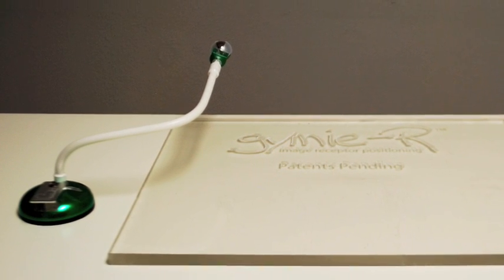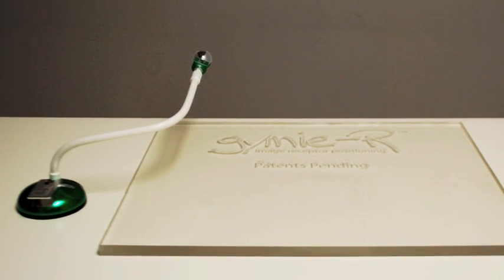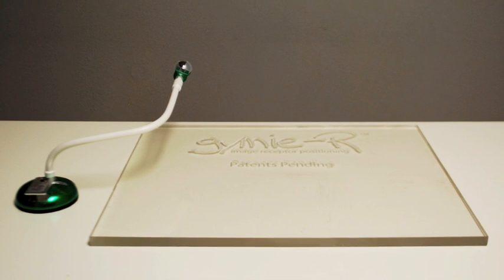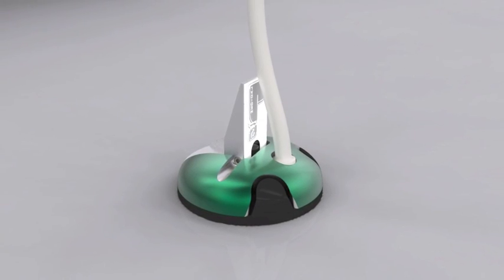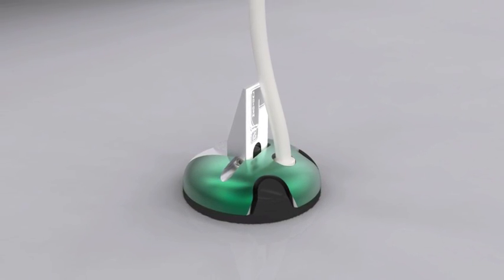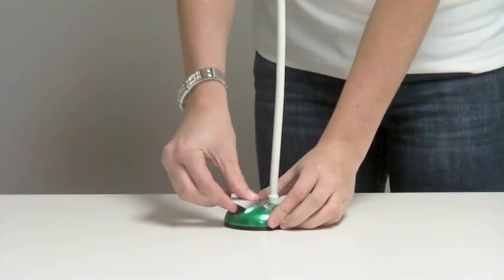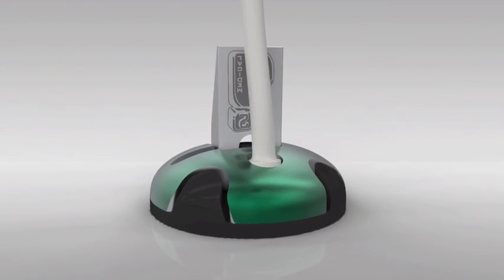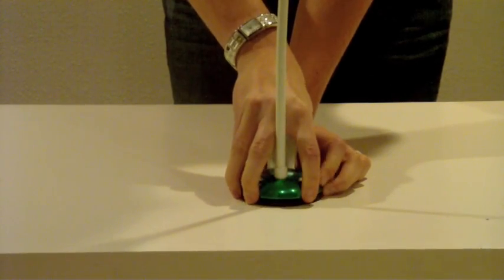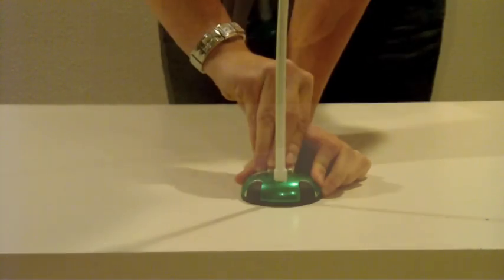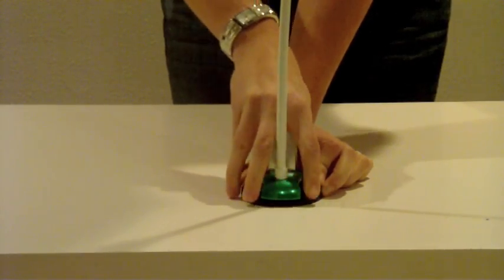Please note that the Akucal should be removed from the table surface or upright bucky after every patient. To detach the Akucal, release the suction cup lever. This can be done by simply lifting the lever up. Grabbing only by the base of the stand, depress each rubber tab to release the Akucal. Here is a demonstration of the Akucal removal without interruption.